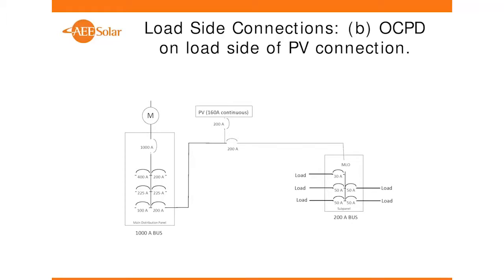The easier and probably the most likely way you would do that is to actually reinstall the feeder breaker or relocate the feeder breaker at the connection point of where the PV system comes in. What this does is maybe somewhat obvious or maybe not obvious, that it protects everything downstream so you can flow no more than 200 amps on that portion of the circuit. This portion of the circuit's fine. This portion of the circuit has to be protected. Therefore, if people overloaded this panel for any reason, then this breaker would trip and protect everything downstream.